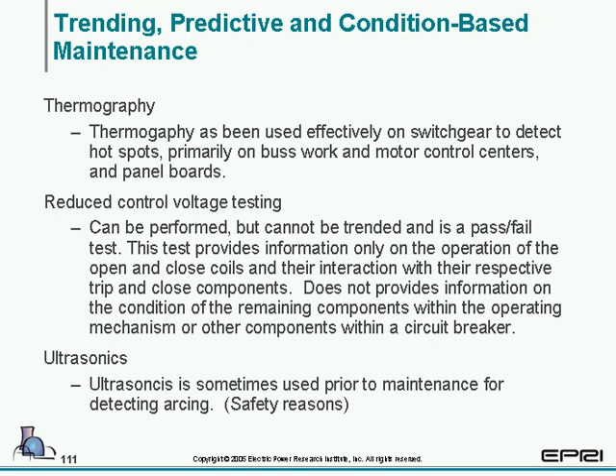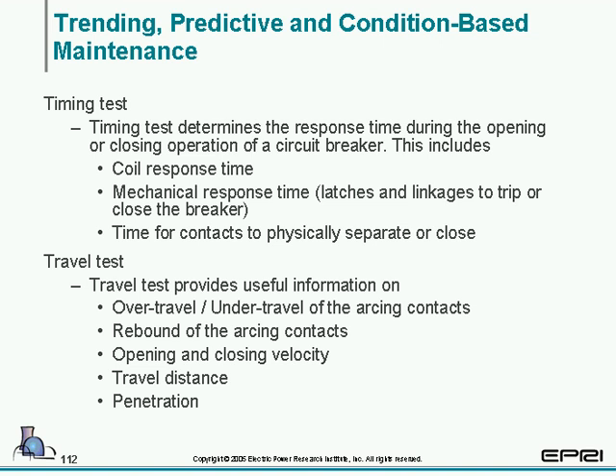There are many components of the circuit breaker that you have to look at. Some plants are using ultrasonics, a very small number, but they are using ultrasonics primarily for safety reasons. Ultrasonics can detect some arcing. There is the timing test. It determines the response time during opening or closing operation of the circuit breaker. It includes the coil response time, the mechanical response time, in other words, how long mechanically the breaker takes to open or close, and time for the contacts to physically separate or close.